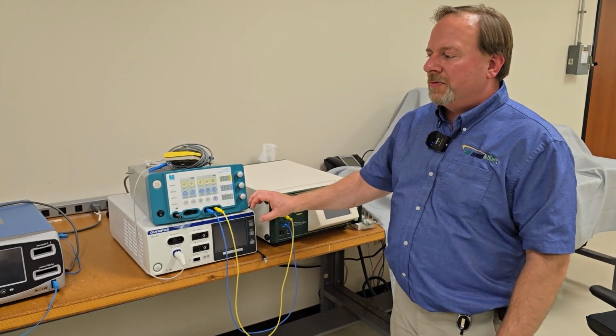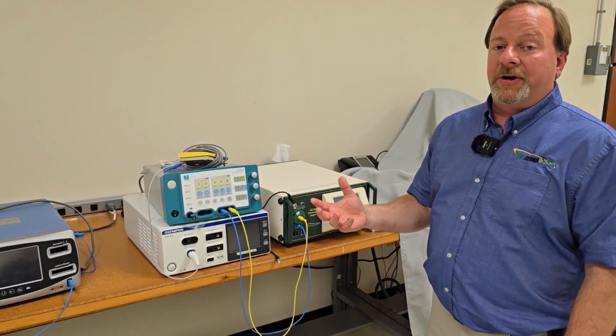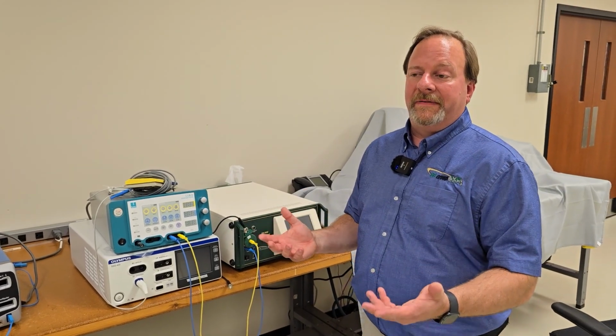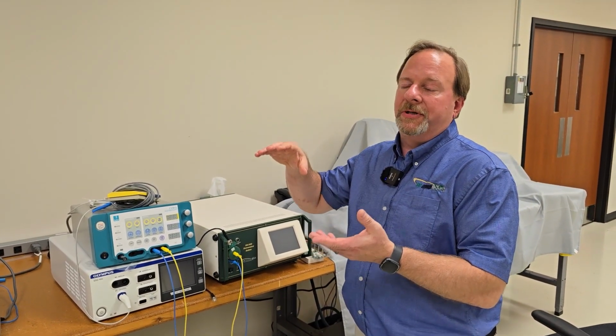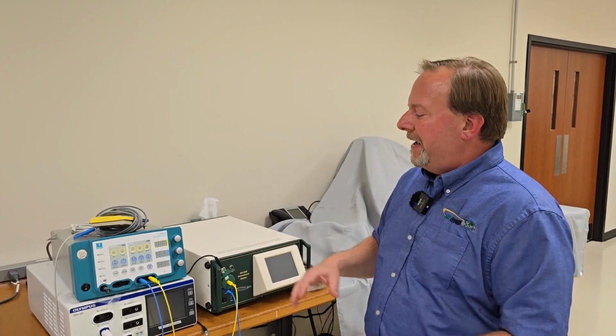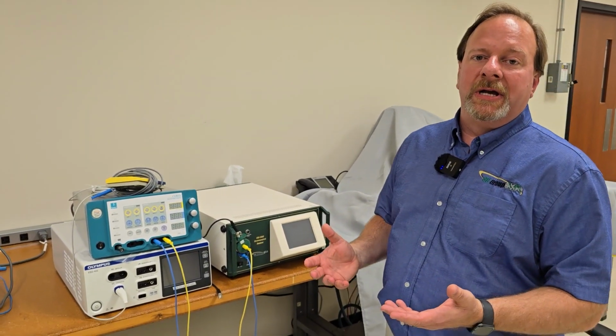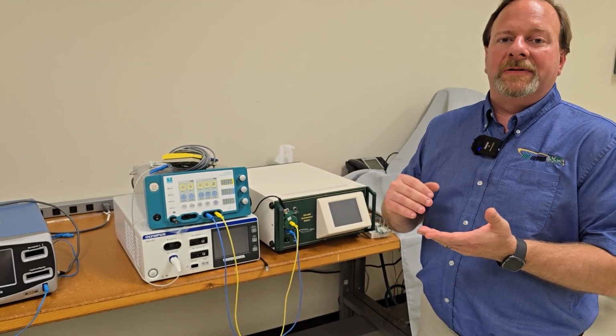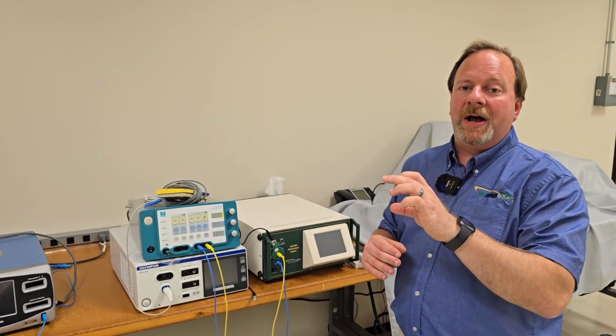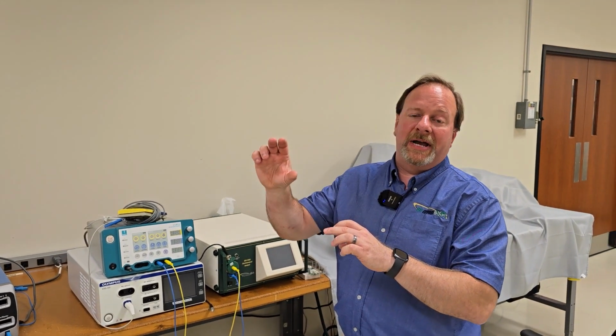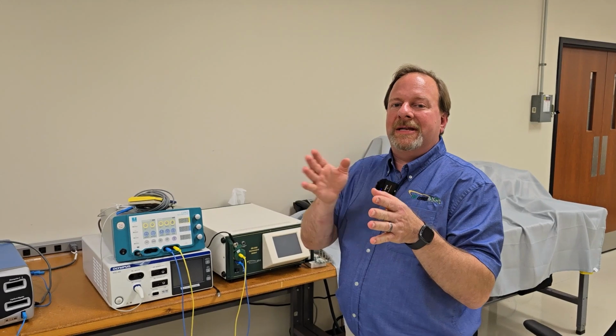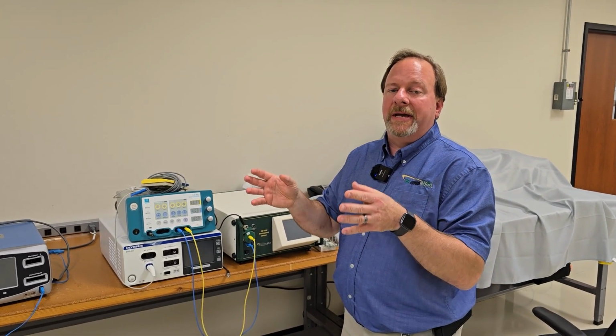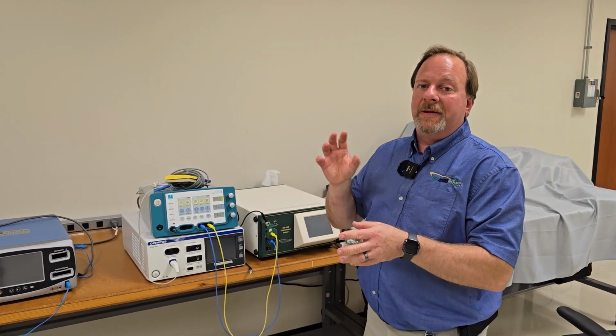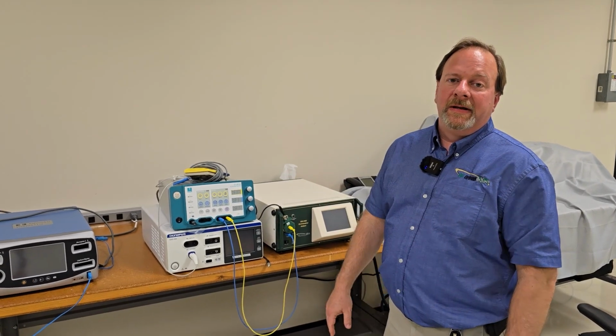But these pulsed waveforms, the 2400 couldn't measure that. And the 2050P, because there were multiple amplitudes, it wasn't just on or off. That's where we developed the 2400H, so we can see the different levels - it may have one section of the output that's 50 milliamps, another section that's 100 milliamps. We can separate those and measure them independently, and give you the timing, the power, and the milliamps in each section.